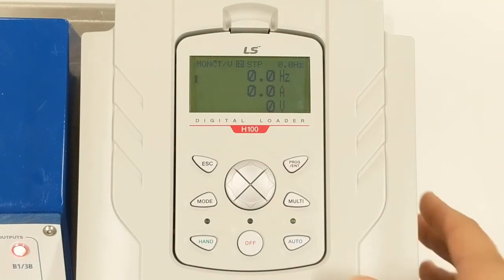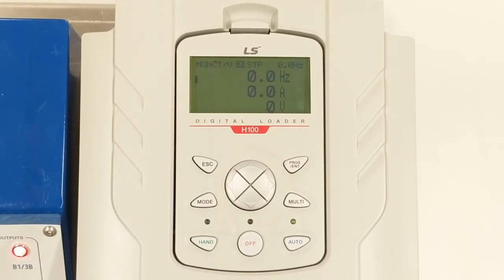Now we can press the auto key and see that at the top of the display it says TV. This means terminal start and voltage source speed control. Your speed reference will change as the signal varies from 0 to 10 VDC. We can start the VFD in auto by flipping a switch or closing a dry contact which is wired up to terminal P1. You will now see the frequency and voltage begin to ramp up. We can also see the amperage that the motor is drawing.